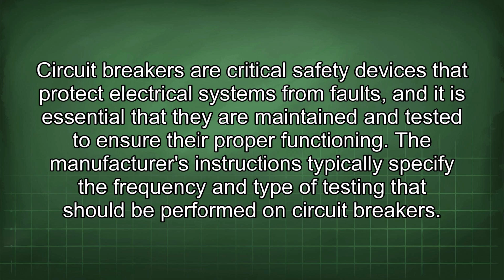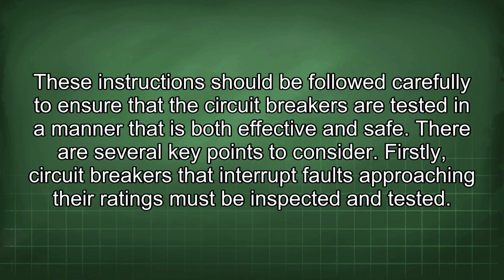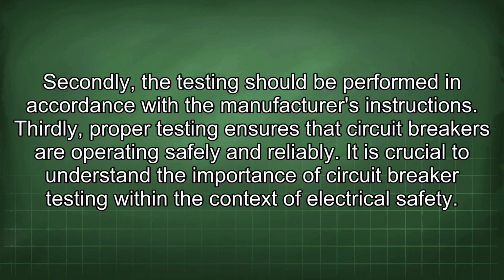The manufacturer's instructions typically specify the frequency and type of testing that should be performed on circuit breakers. These instructions should be followed carefully to ensure that the circuit breakers are tested in a manner that is both effective and safe. There are several key points to consider. Firstly, circuit breakers that interrupt faults approaching their ratings must be inspected and tested. Secondly, the testing should be performed in accordance with the manufacturer's instructions. Thirdly, proper testing ensures that circuit breakers are operating safely and reliably.